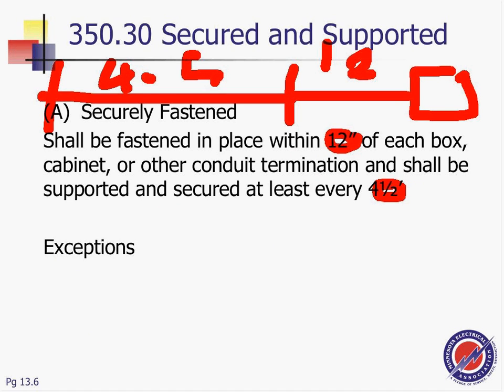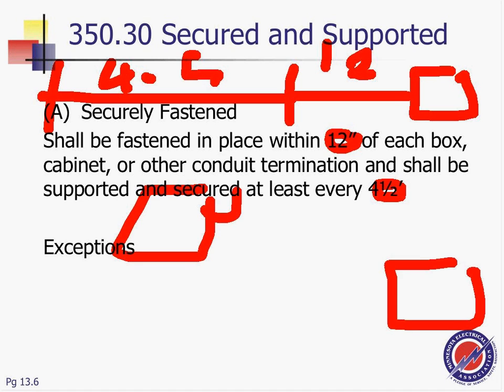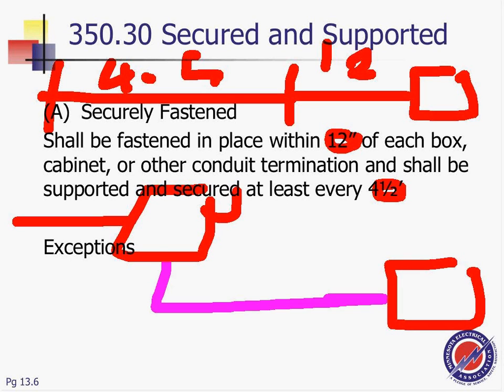For support number 1, in a wall, you don't need to support it because it's practical. If you are tying it for equipment, for installation, where flexibility is needed. So equipment, here's my disconnect switch, and we pull conduit here, and this is my cable. We can go all the way. This could be 3 feet, depending on the size.